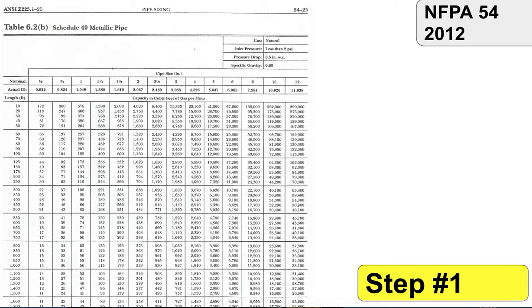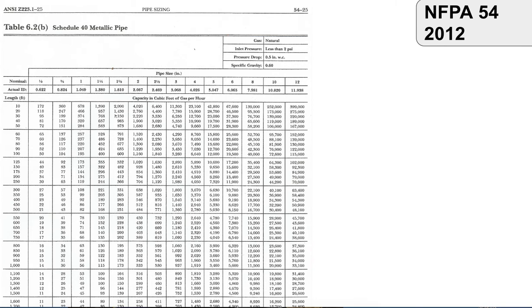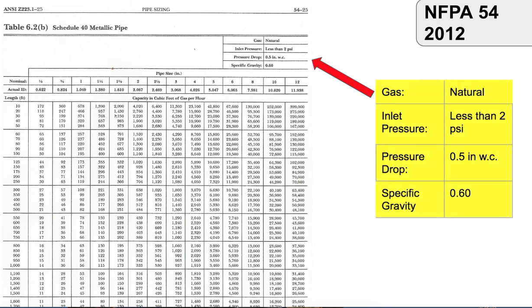When utilizing these resources, you just have to take a couple of things into consideration. Some basic stuff: make sure when you're going through the pages to size your gas pipe, you're on the right page as far as the material you're using. If you're using black steel schedule 40 metallic pipe, that's the page you want to be on. You also want to make sure you're on the natural gas page and not propane.